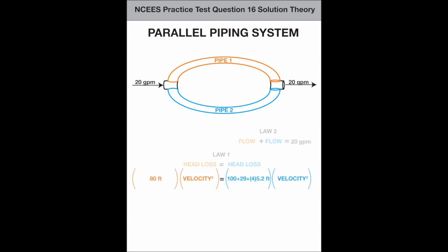Set this equation up. Divide. Square root. So the ratio for balancing is roughly 1.37. That means branch A's flow equals 137% of branch B's flow.